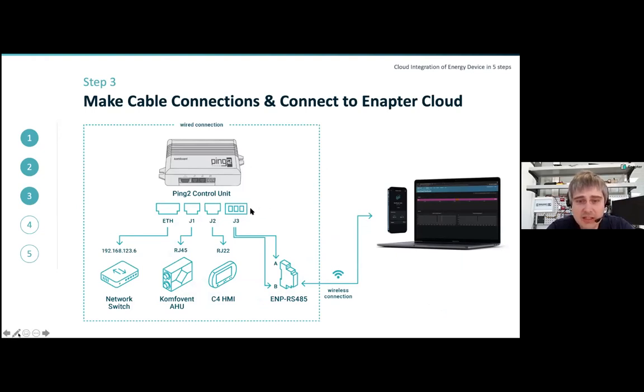So we connect the J3A wire to the A terminal block on the ENP RS485, and the B cable to the B connection on the module. On the other hand, the Ping2 control module is connected to the existing C4 human-to-machine interface for the ventilation unit, and also to the network switch with IP address 192.168.123.6. We'll use the connection to the web interface of the Ping2 module to control the system, because it's actually located 20 kilometers away from me at the moment.